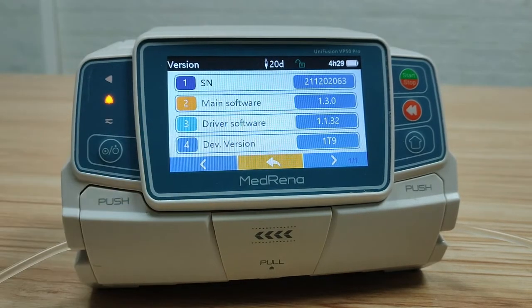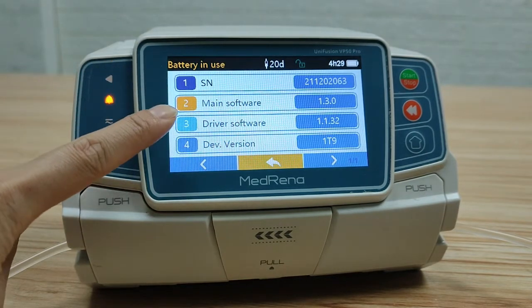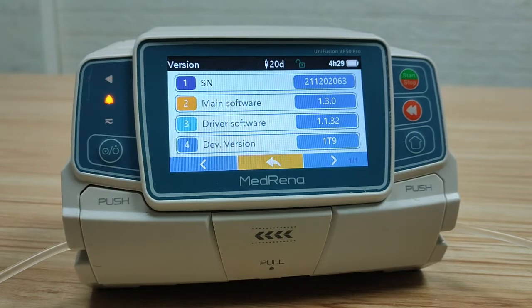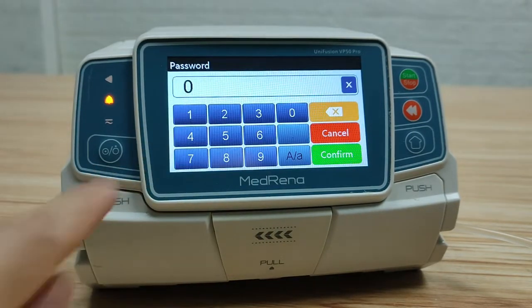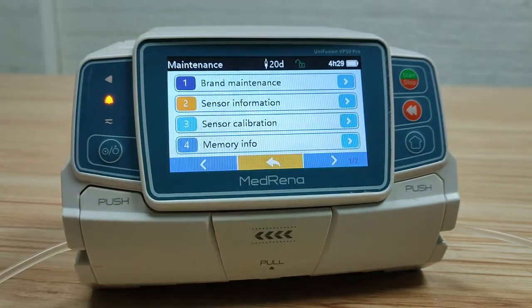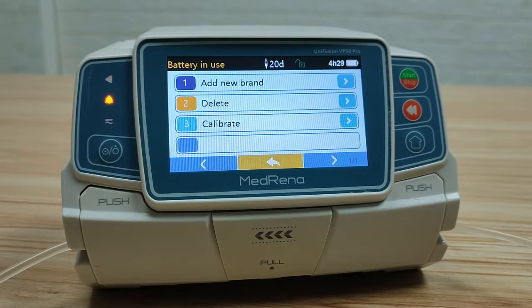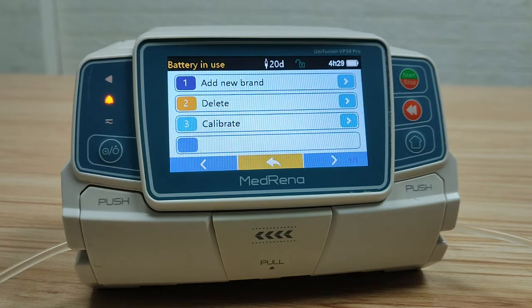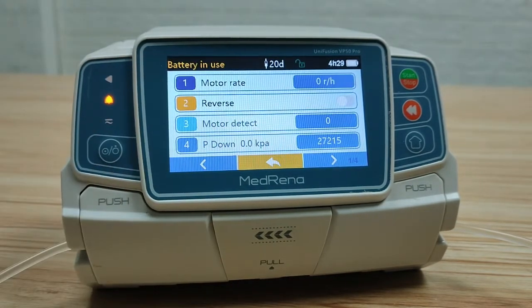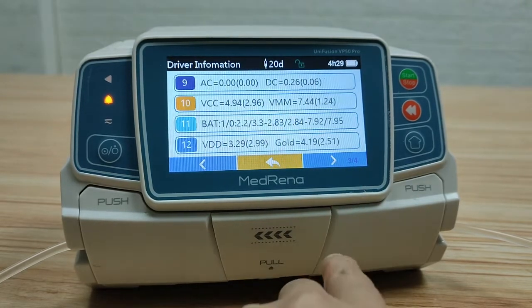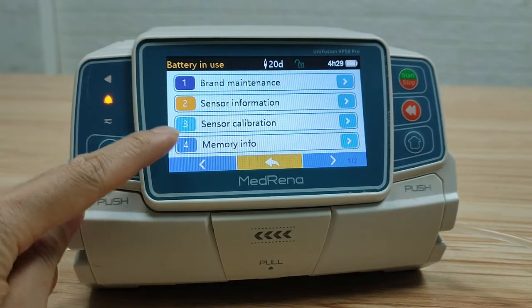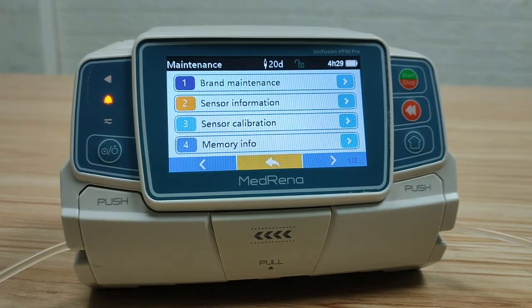Version: here it shows the serial number, the software version, and the device version of the pump. Maintenance: enter the password. There are different settings under this item. First, brand maintenance — we can add, delete, and calibrate infusion set brands; we will explain how to add an infusion set brand and calibrate it in the next video. Sensor information: here we can find current settings of different sensors and modules, sensor calibration, and memory information — please leave these to the service engineer when repair is needed.